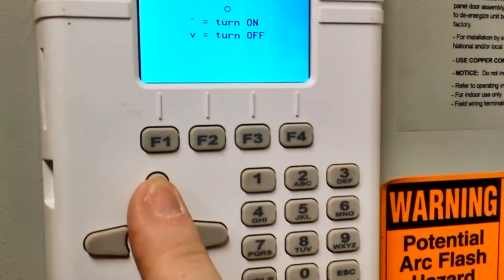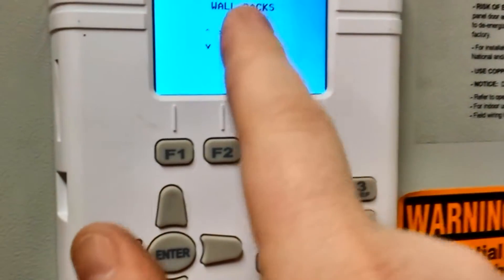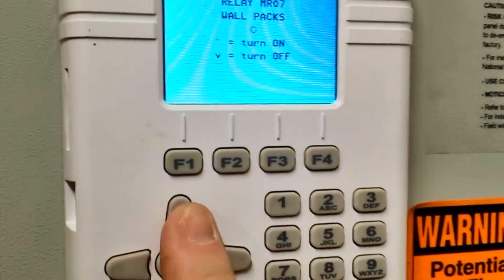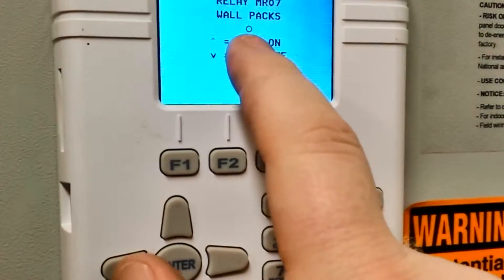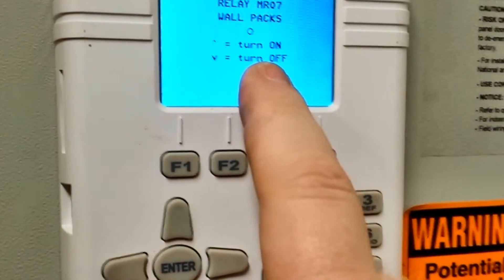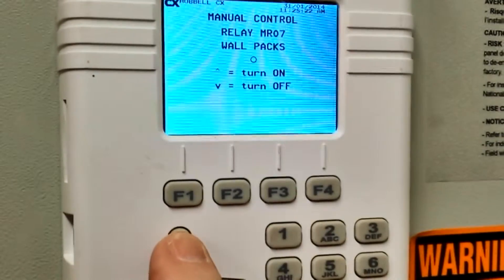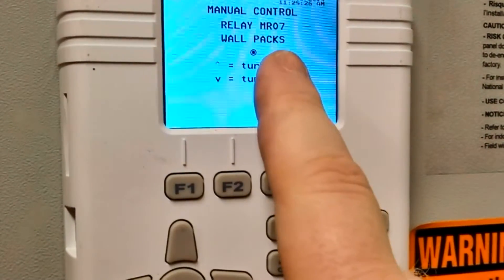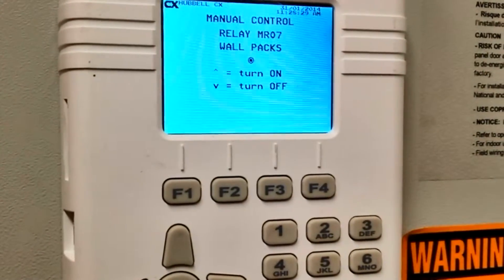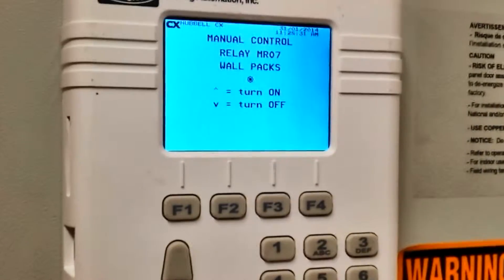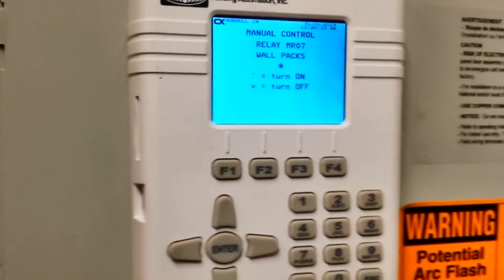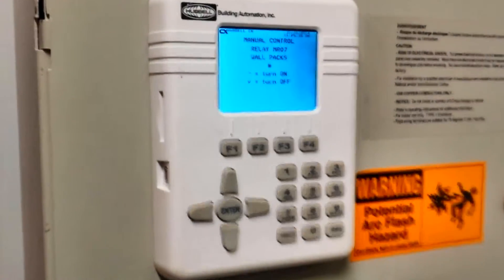To turn it on, I'm simply going to push the button. Watch this little circle here, because this will give you an indication of exactly what it's doing. Right now there is no dot in there, so that indicates the relay is off, but when I push the button you will see a dot appear. As you can see, the dot is there — we know that this relay works. It has been verified with a voltmeter, but that is simply how you will override a relay in one of the Hubbell CX lighting panels.